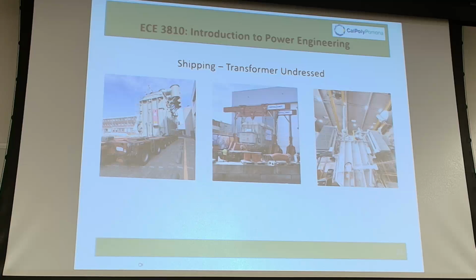This was a funny picture. I don't know why the angle is really weird. The one thing you get when you go see this is the sheer size of it. If you walk in there, you go, holy moly, these things are ginormous. They're really, really big. And that's what I was telling you guys, designing one of these things. Right now, for 250 MVA, I'm going to put that on single phase boxes. About 5 years, we have a project right now with SCE and LADWP. I think 2028, 2029 is when they're going to be delivered. So it does take a long time.